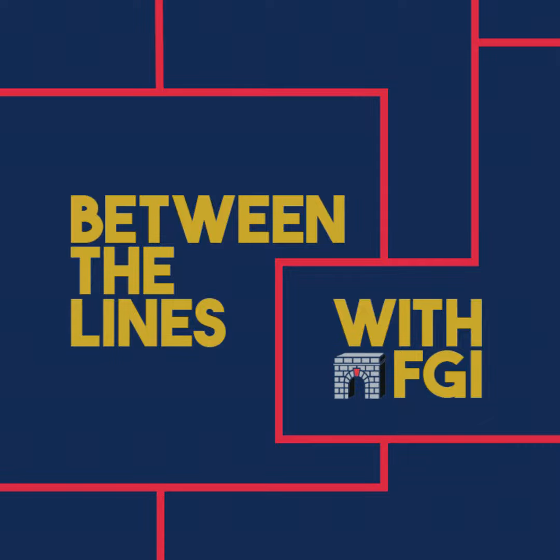So help me understand, what would be a situation where there would be trivial amounts of cryogen? So helium is a finite resource on planet Earth. We used to have what we thought of as a limitless supply of helium because of this huge national stockpile. Turns out it's not as forever long-lasting in quantities as we thought. And there have been intermittent helium shortages with supply chain issues and that kind of thing. So the MRI manufacturers recognize that as a potential weak point in facilities' ability to keep their MRIs going. There have been a number of facilities that have had quenches, and because of service contractors' inability to get sufficient quantities of liquid helium, the MRI is down for a protracted period of time.